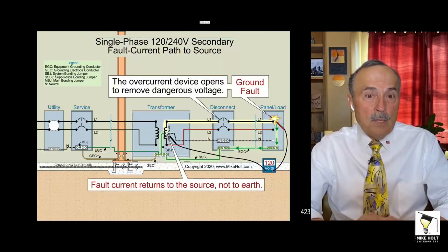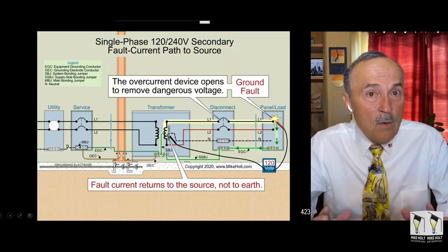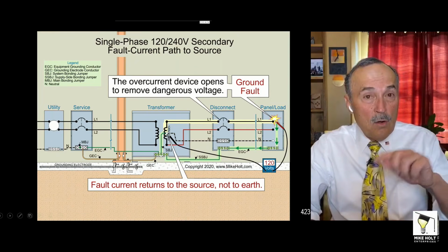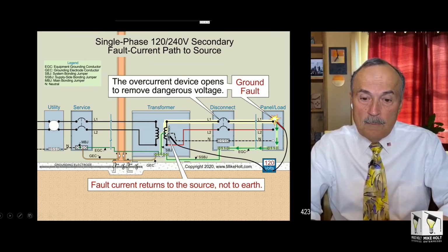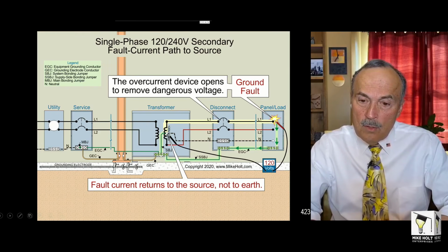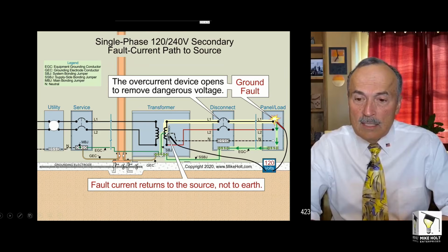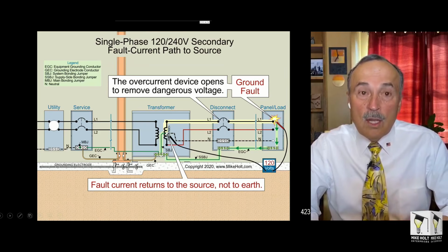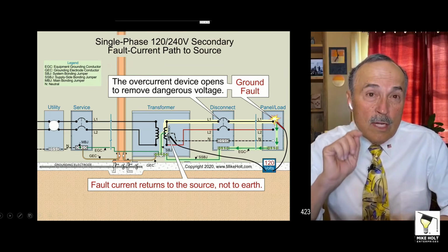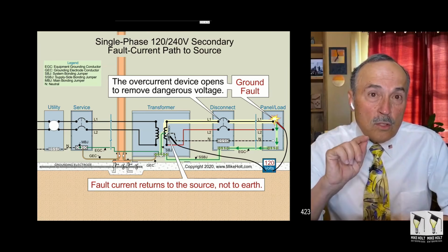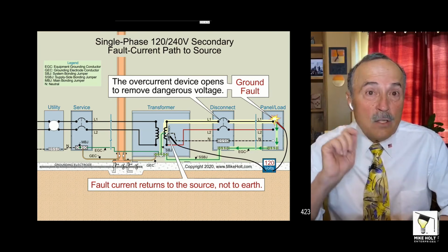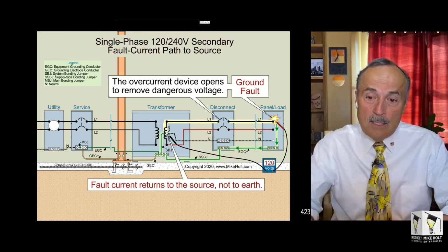All right, looking at the example here, what happens is a fault, a ground fault, which is defined by Article 100, which gives us a definition. Electrons leave the transformer, go to the line 1 overcurrent protection device to get to the enclosure. There's a ground fault. Ground fault current is going to the source. Ground fault current is not going to the earth. You can just watch the path here.